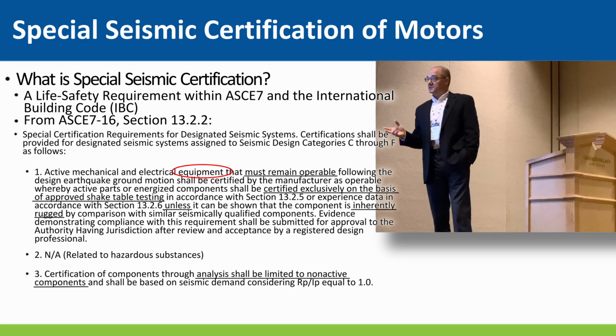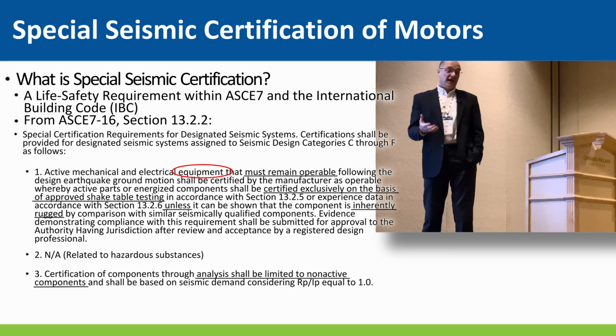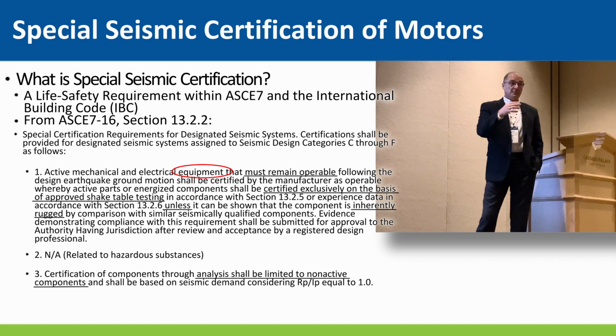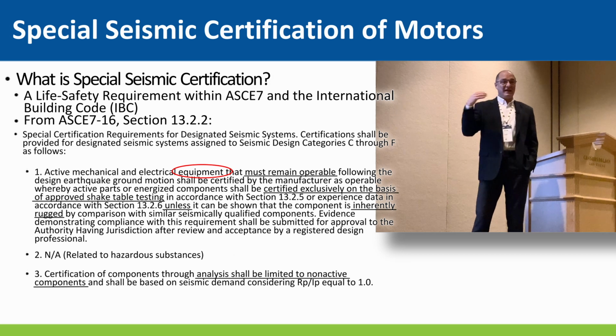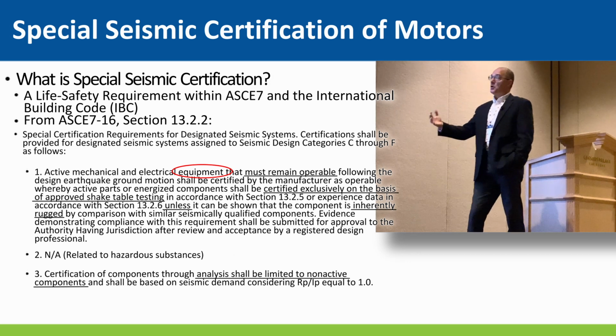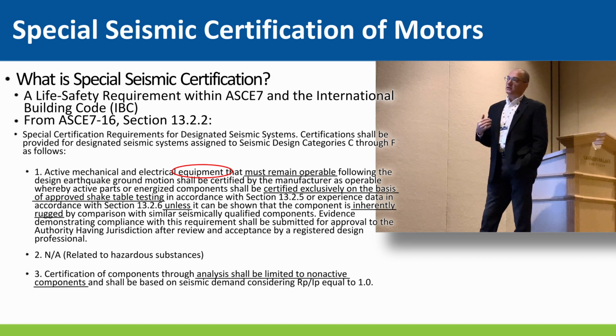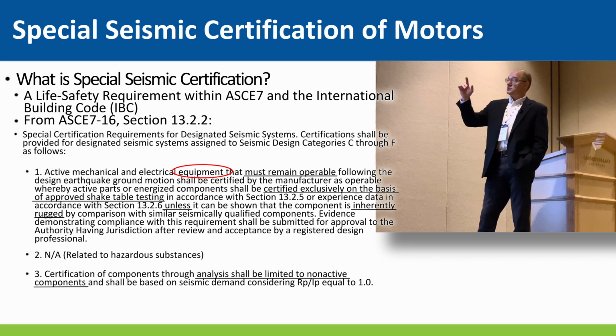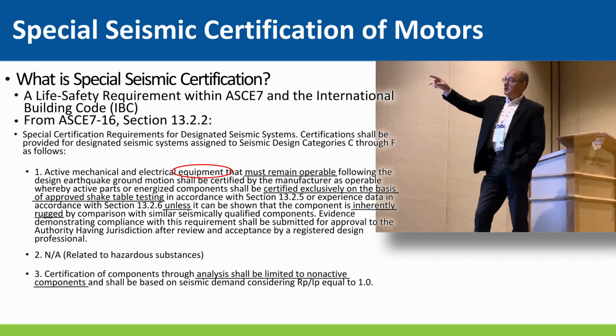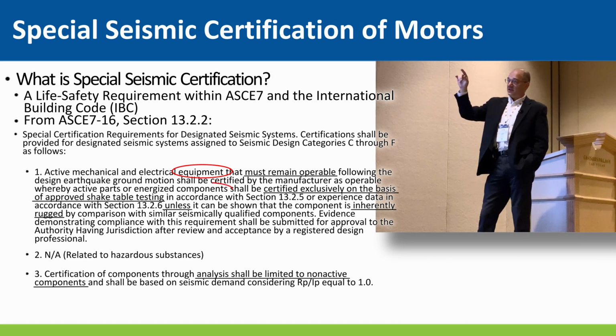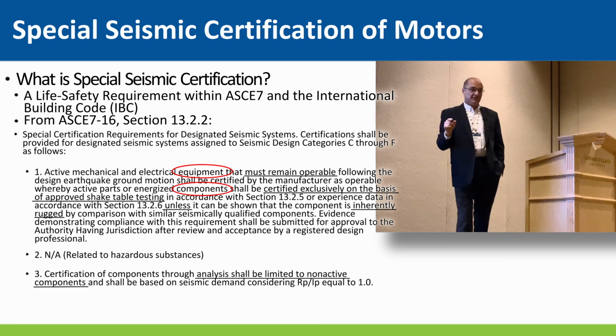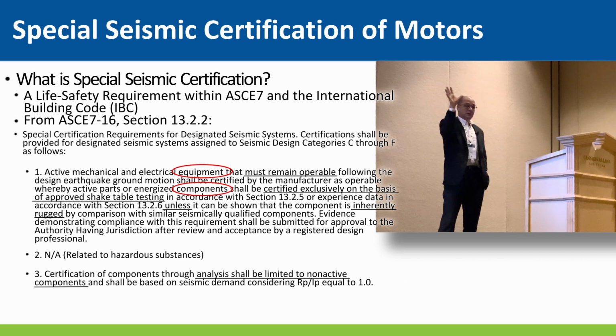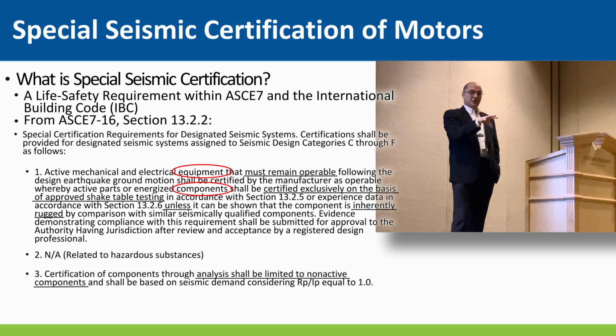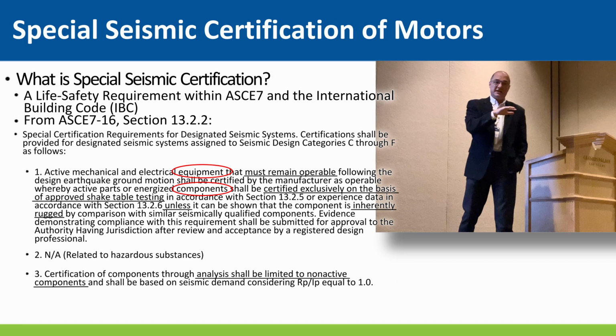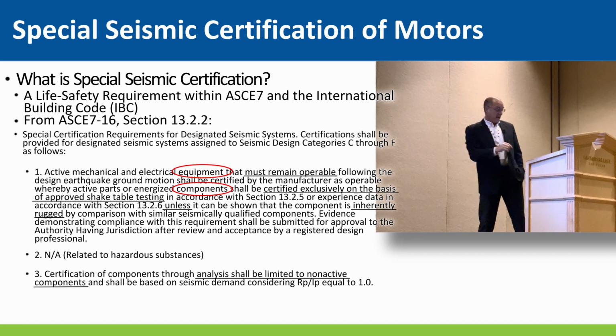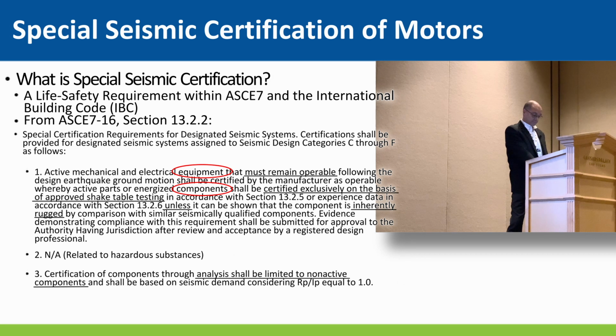First of all, we've got two different terms, equipment and components. So if we step back and think about it, your motor is a component within a piece of equipment. So now we reword this thinking, well, my motor is not the equipment, my motor is a component. So now I'm part of that second sentence, whereby active parts and energized components are certified exclusively. So now they're going within the box. We've got this big piece of equipment, and within that box is my motor. Now the code is talking about what's inside your box, or the box that your equipment, your component, is going into.